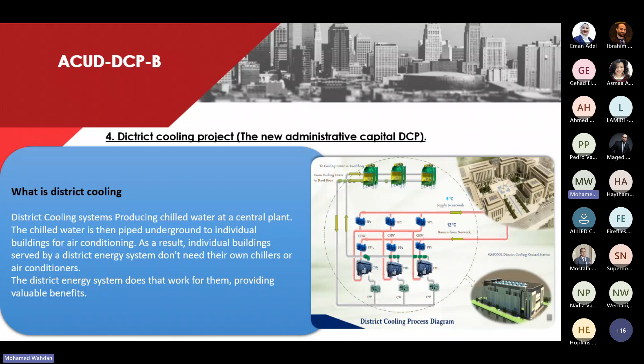The district cooling plant has many benefits. First, improved energy efficiency, as it is better to have one district cooling plant with its main equipment, chillers, cooling towers and pumps, than if every individual building has its own plant. The consumption of energy may be reduced to half.